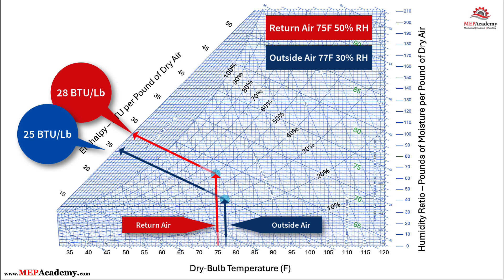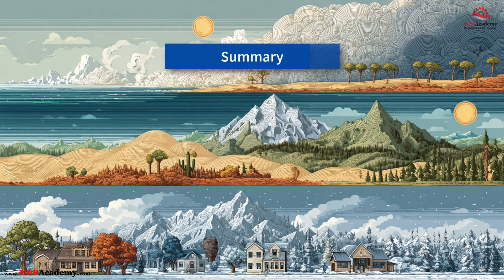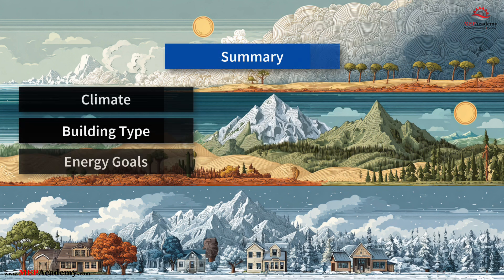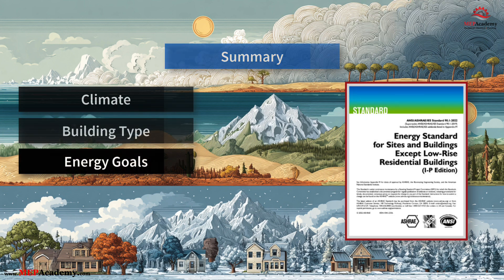This is exactly the kind of situation where enthalpy-based economizer control makes the right decision, while a dry bulb-only strategy could make the wrong one. These conditions happen often in dry or semi-arid climates, where the air can be warm but still very dry. This example is a good reminder that both temperature and humidity play a role in determining the best air source for cooling efficiency. Selecting the right high-limit strategy for an air economizer depends on climate, building type, and energy goals. Fixed dry bulb offers simplicity and is widely recommended across climates with optimized set points at a lower initial cost. Differential dry bulb provides better adaptability but falters in humid areas. Fixed enthalpy addresses humidity but suffers from sensor reliability and is often outperformed by simpler methods. Engineers should conduct site-specific analyses, considering standards like ASHRAE 90.1, to balance first costs, maintenance, and energy savings while ensuring indoor air quality.